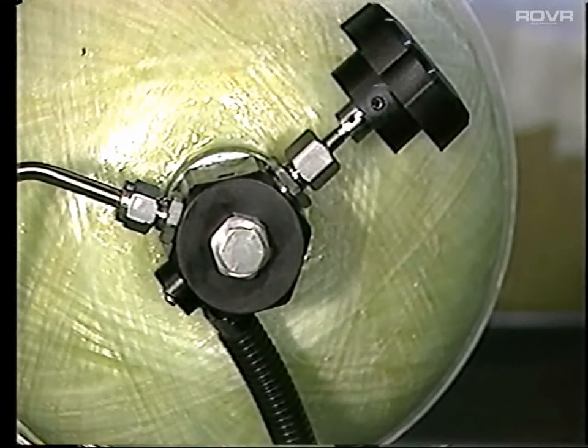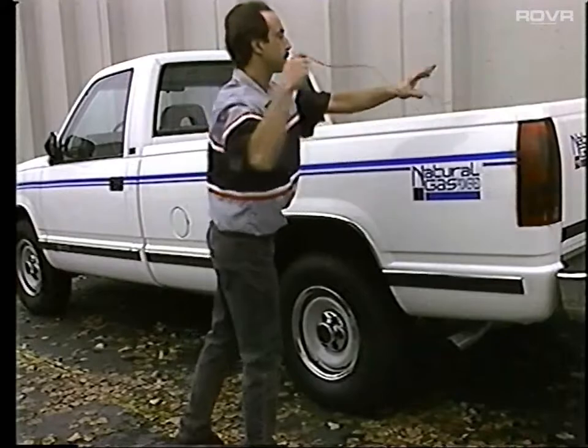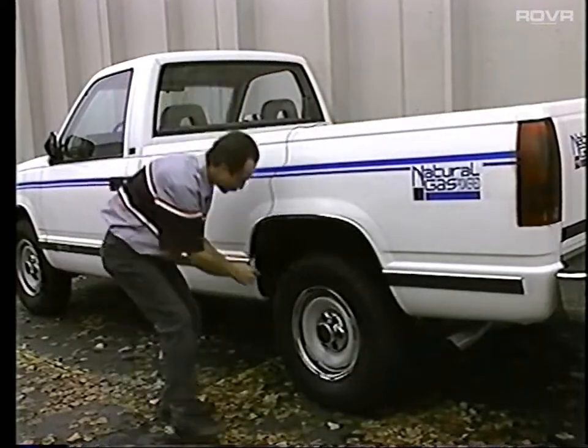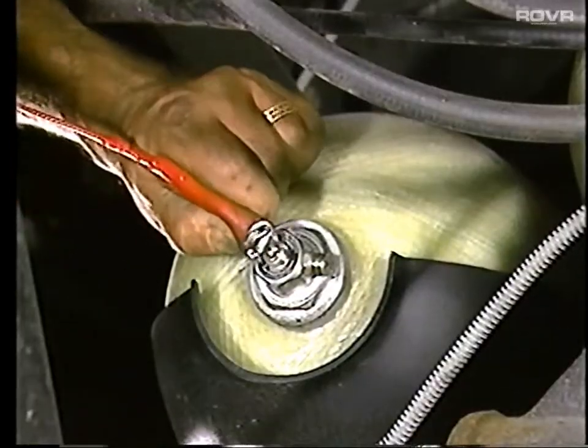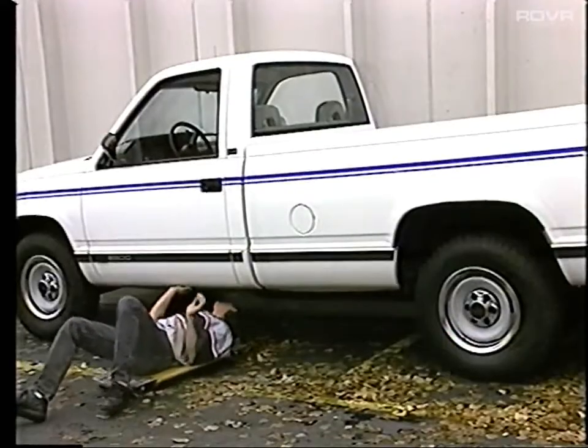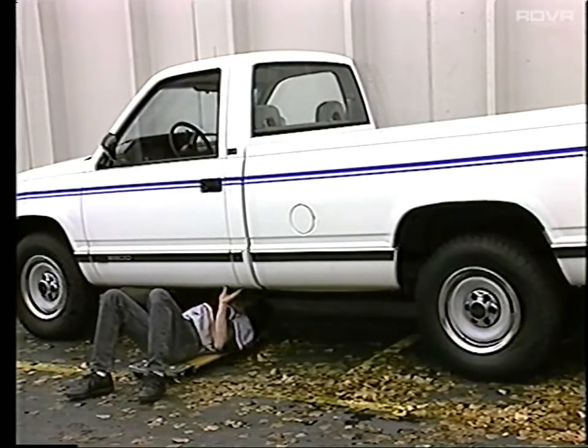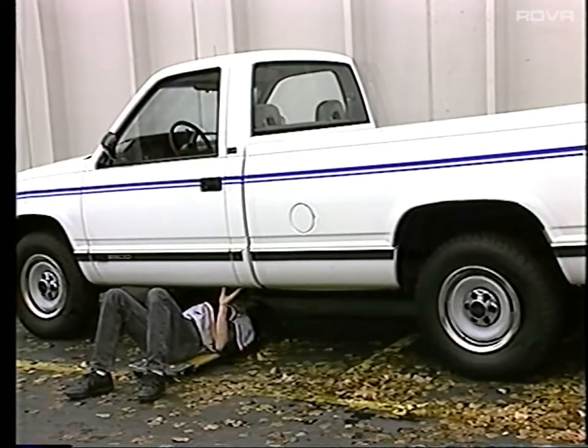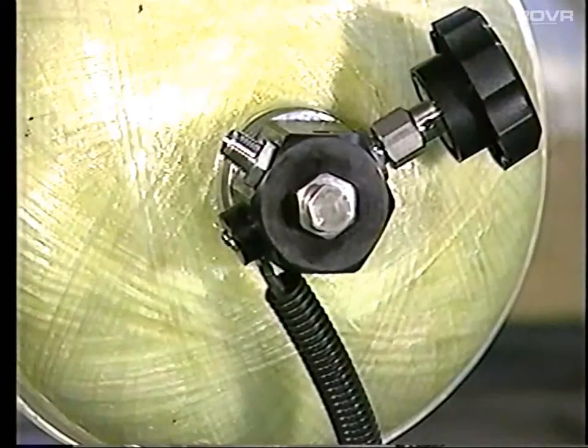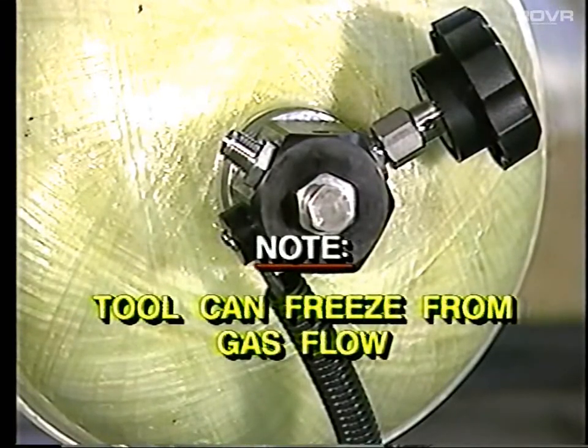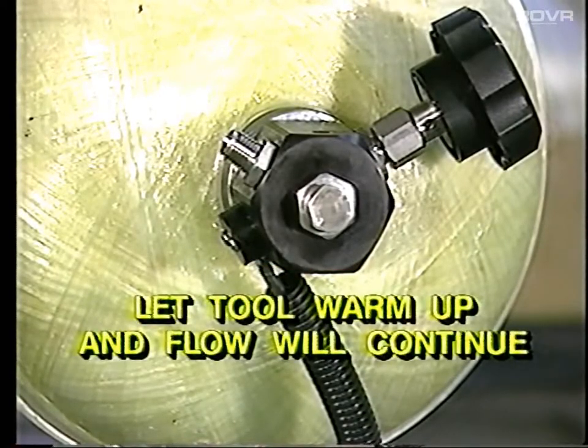However, don't vent the tank yet. Take the truck outside of the service area and ground the system to a good earth ground. Now you can open the valve using the tool. This tool allows for a controlled release of gas from the tank. Note, this tool can freeze with the gas flow and stop venting. If this happens, just let the tool warm back up and the flow will continue.